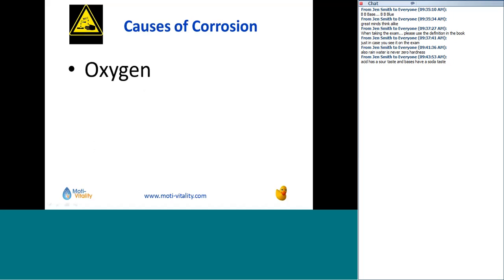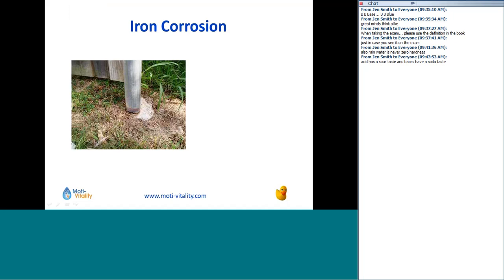Dissolved oxygen in the water will absolutely cause corrosion. I have a customer here in Michigan that has a ton of dissolved oxygen in the water, and you should have seen the havoc it wreaked on their plumbing system. Incredible. It just destroyed their copper plumbing. Acids will also cause it, and galvanic action.